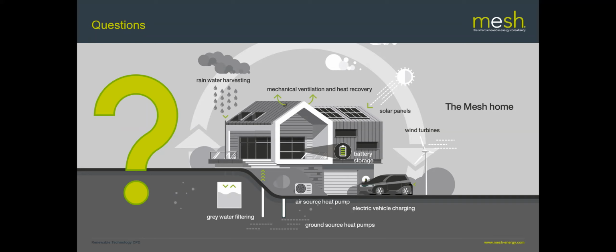Yeah, okay. I think that covers off all the questions. Alex just makes the point that there are passive house rated combined intake and outlet that have been used. As I say, I would assume that where they have been used, they must have some internal design feature that separates those airflows and makes sure they blow in opposite directions, to ensure that you don't get short circuiting. But it's not something I've personally specified. I would always separate them by at least 500 mil and preferably more.